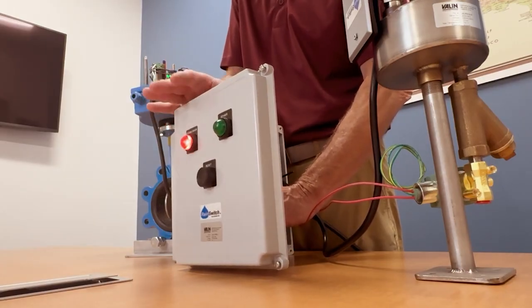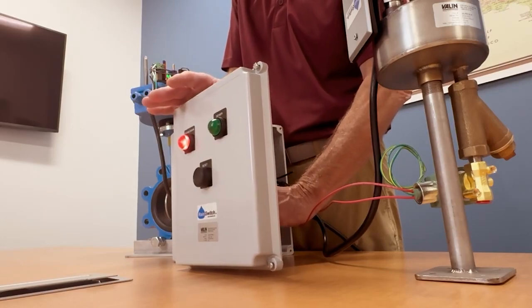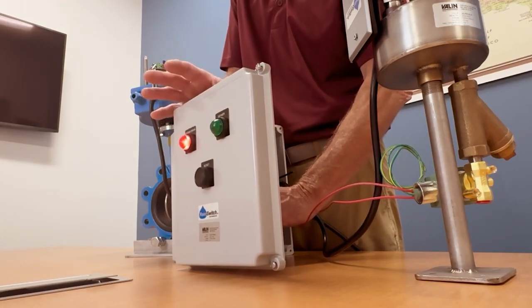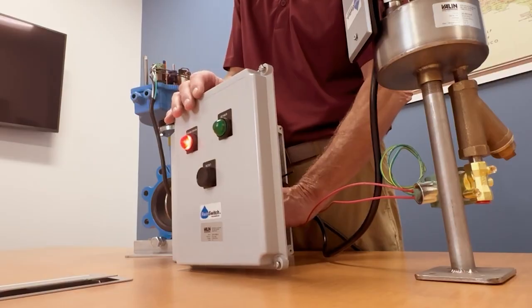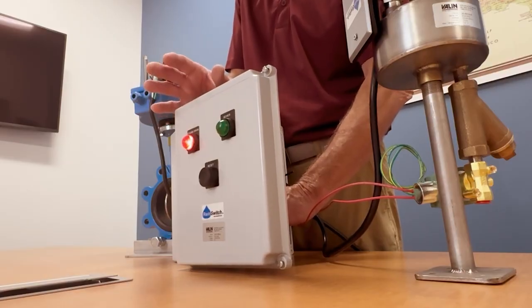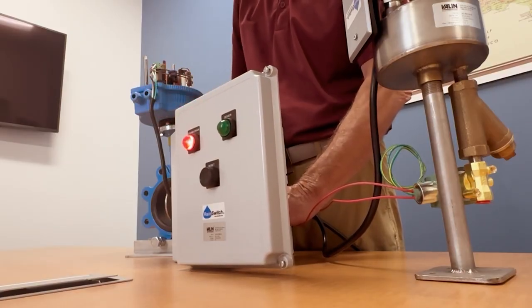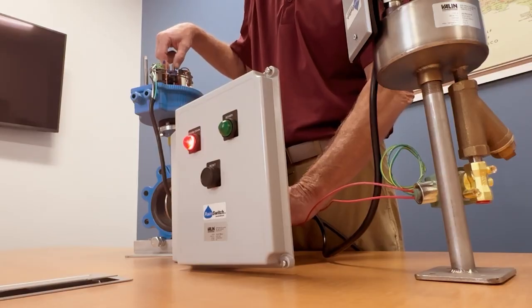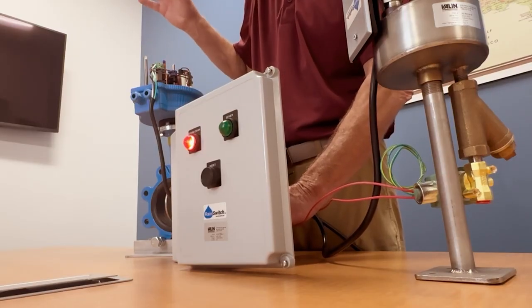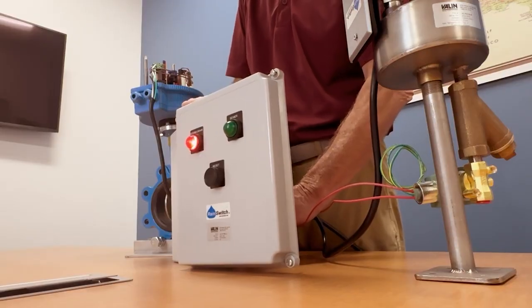So if you ever come up to the system and you have no lights, you either have a bad light, which is doubtful since they're LEDs, they last forever, or the valve is jammed in mid-stroke, it's not reaching its full open or closed position, or these cams are out of adjustment. There's no reason for them to go out of adjustment, but that's a possibility too.